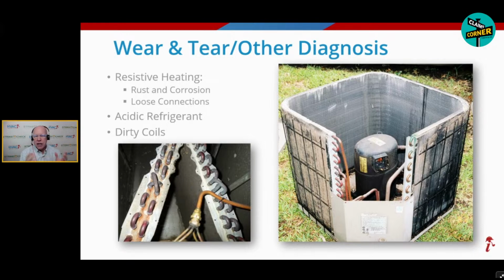If you've taken our fundamentals class, which I think I did last year here at Claims Corner, we talked about having to have the flow of air through the coils, both the outside coil and the inside coil - that's where we're transferring heat. Remember, these systems are not generating cold air, we're moving heat from the inside to the outside in cooling mode using the refrigerant, but that means the air has to touch these coils so we can get the heat out of the air into the refrigerant and move it outside. If they're dirty like this, the air can't touch the coil.